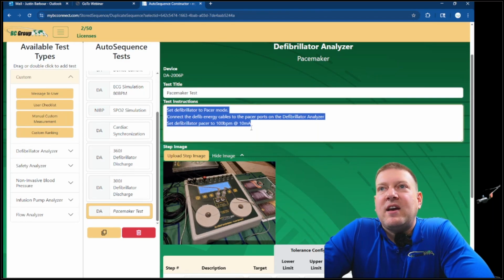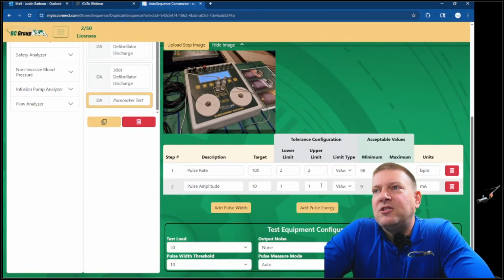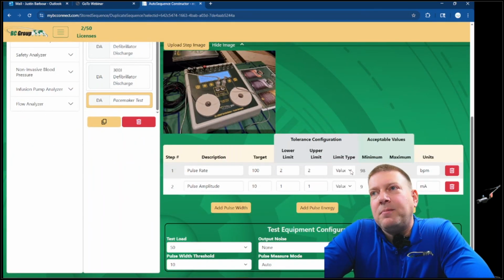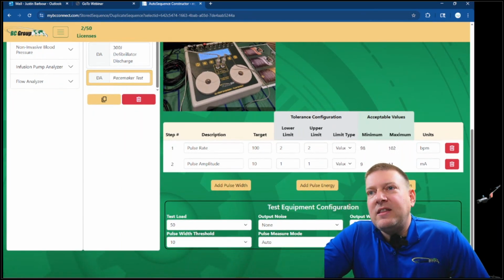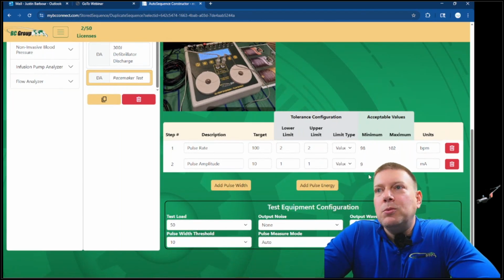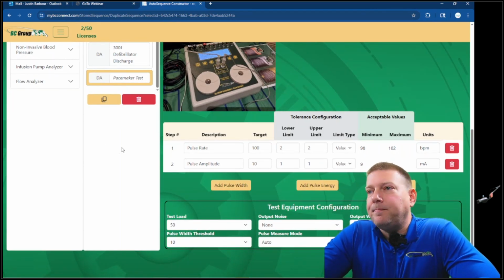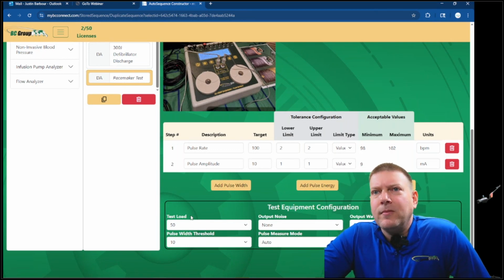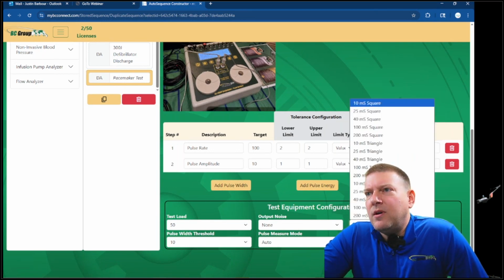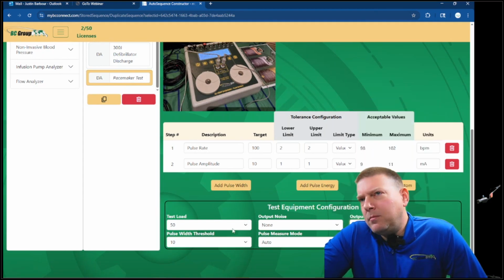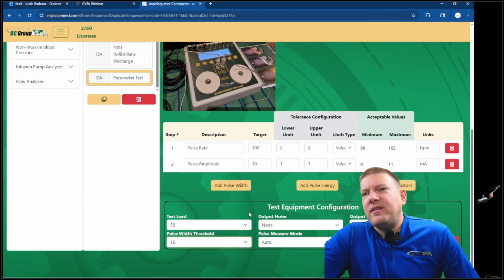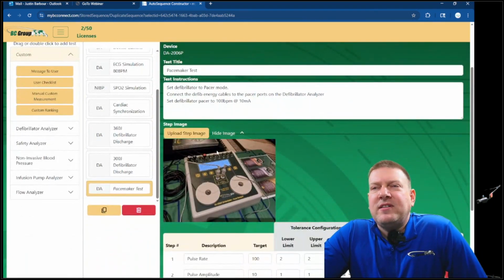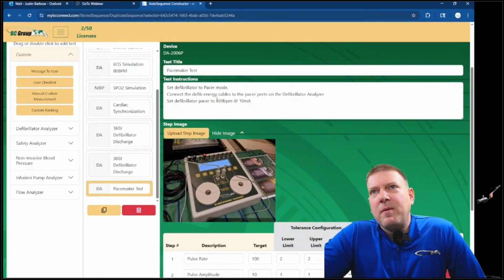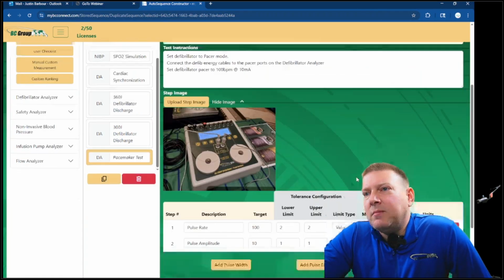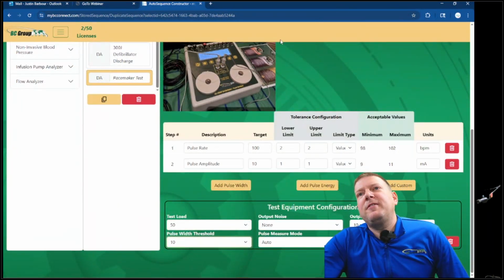And then I tell them exactly how I want it set up. And it's going to automatically measure the pulse rate and the amplitude down here. I've got my specs set up, so it's pass or fail. You'll get that result, and you will complete the test with this one. And it's very simple. Test load, 50 ohms, 10 millisecond square wave. That's pretty fair. Pulse width, there's a lot of options there. You don't really need to do that in order to test pacer. As long as you set the defib up to 100 BPM and 10 milliamps, it will automatically give you a pass or fail as soon as it detects a pulse.